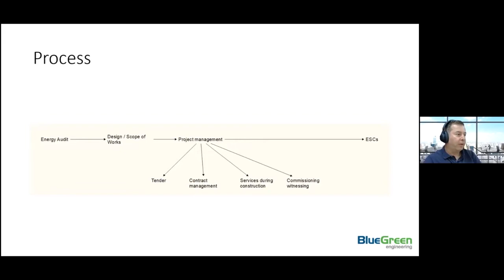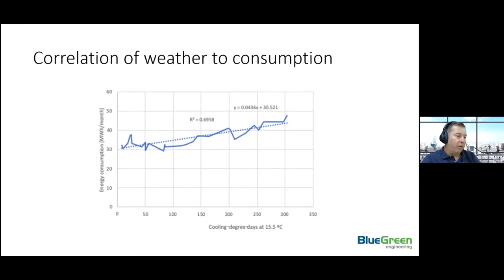So one of the findings of the energy audit is this graph here, which shows how energy consumption is correlated against weather, whether we express this via cooling degree days. We expected to see a line that is correlated to the dotted line, and the correlation was not that great. This showed that if the weather was hot, the energy consumption would not increase, and also if the weather was too cold, the energy consumption would also not increase. So we dug further into this.